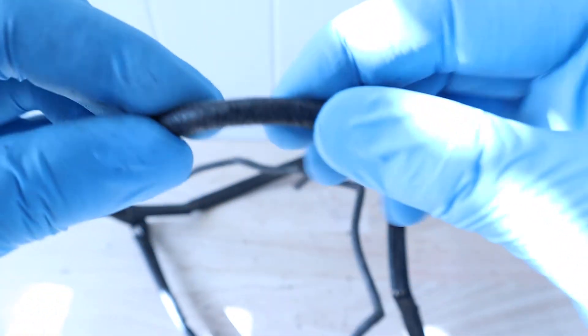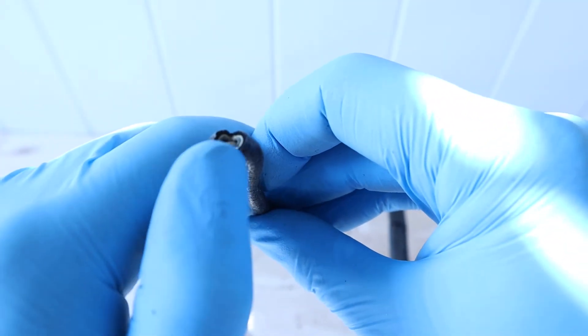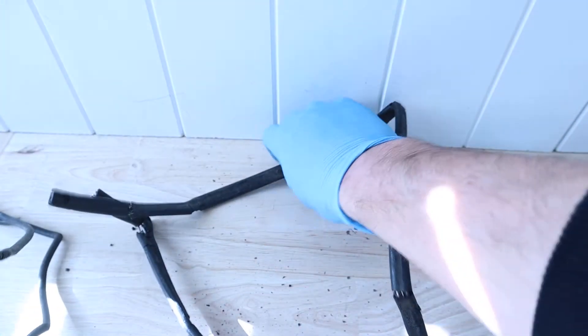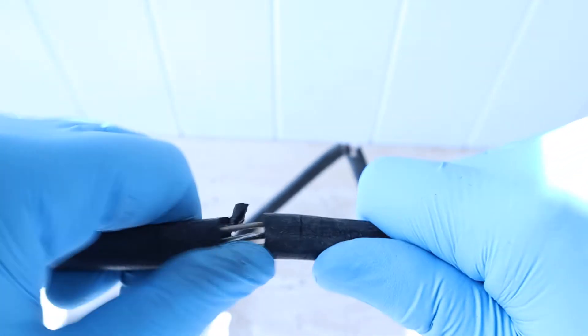So I take this conductor and I just bend it. You can see that's exposed—that live conductor inside there. So it's very, very brittle, this stuff. This was on a power circuit. I'm gonna bend that and then it just totally exposes that, and that just peels right off. So that's how brittle it is.